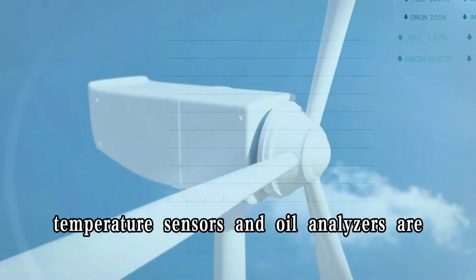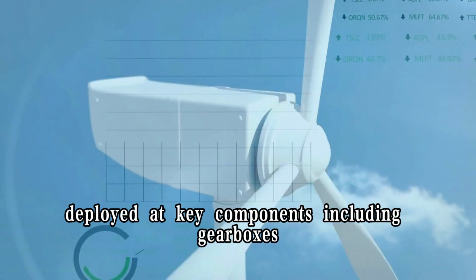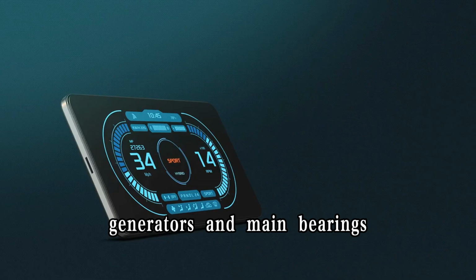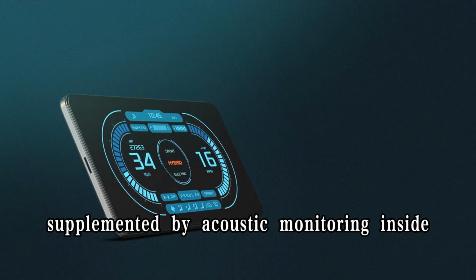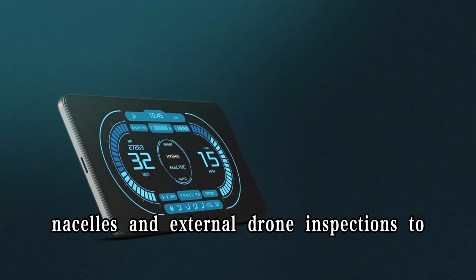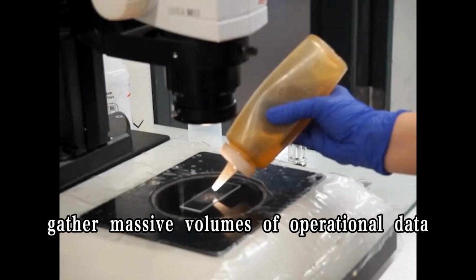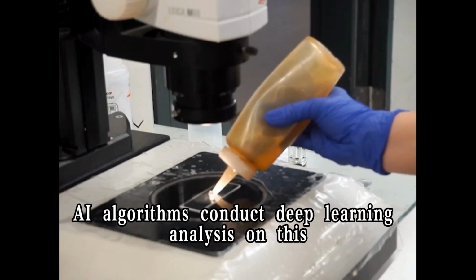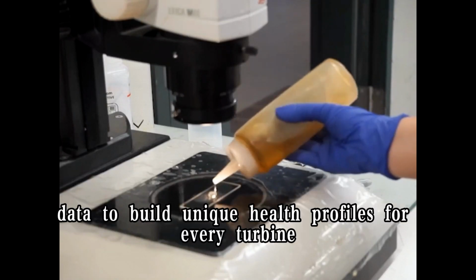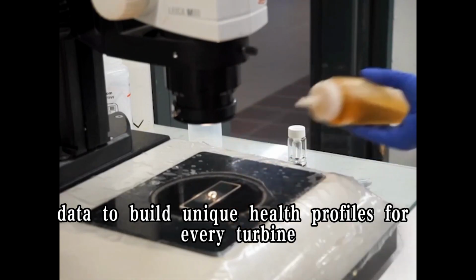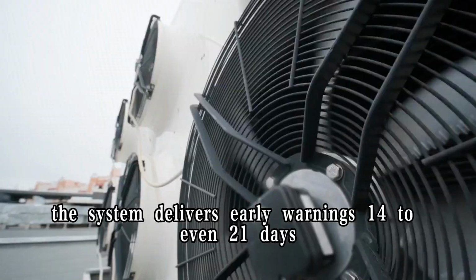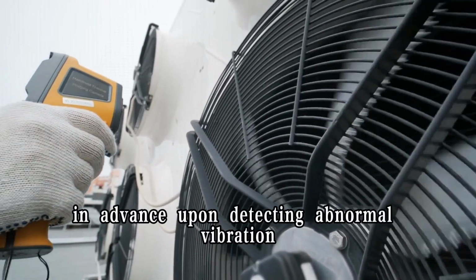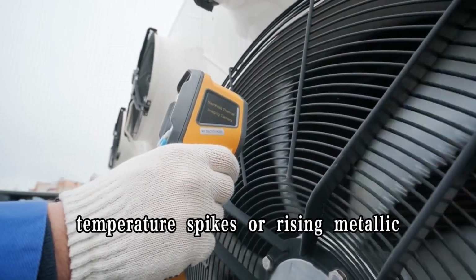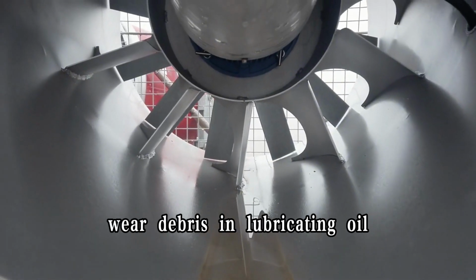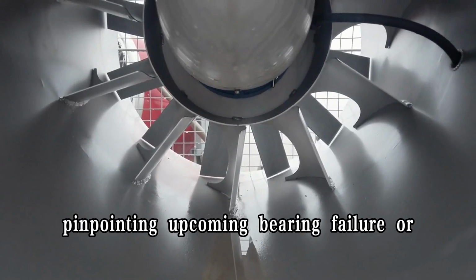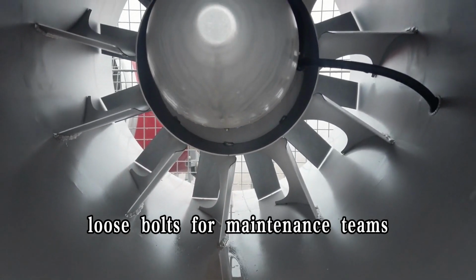Vibration sensors, temperature sensors, and oil analyzers are deployed at key components including gearboxes, generators, and main bearings, supplemented by acoustic monitoring inside nacelles and external drone inspections to gather massive volumes of operational data. AI algorithms conduct deep learning analysis on this data to build unique health profiles for every turbine. The system delivers early warnings 14 to even 21 days in advance upon detecting abnormal vibration, temperature spikes, or rising metallic wear debris in lubricating oil, pinpointing upcoming bearing failure or loose bolts for maintenance teams.